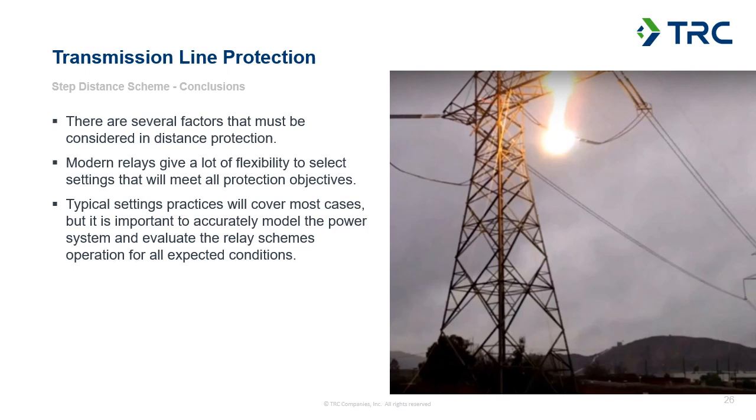Lastly, the typical settings practices are going to cover you for most cases, but it's important to understand some of these unique factors and accurately model the power system, so that you can evaluate if those typical settings, philosophies, and practices are going to be adequate for any application, even if it seems very straightforward.